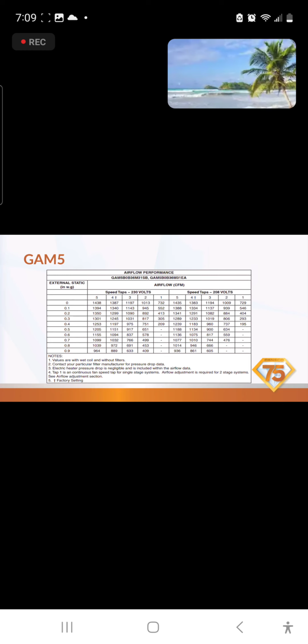So please, when you're setting these up, take the time to verify your voltage, verify what speed tap it's currently on, turn it on and check your static pressure, and then compare that to the chart and the service facts, and that's going to give you your CFM. If you don't take the time and do all these things, it's just a guessing game, and that doesn't help anybody out. It doesn't help you out. It doesn't help the homeowner out. It only causes callbacks, and I know nobody wants those.